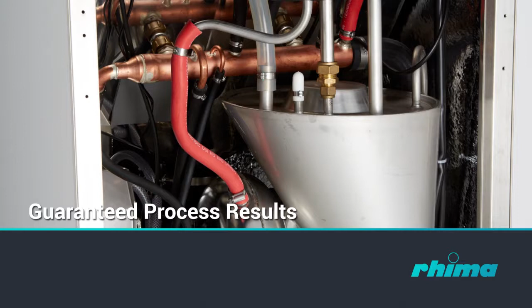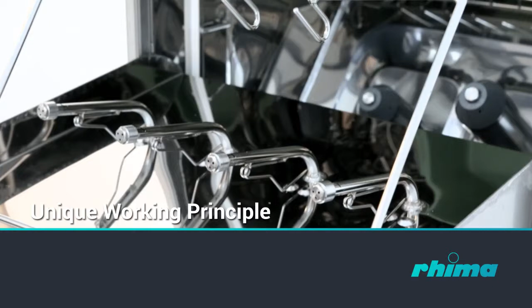Process results are guaranteed. Water pressure for washing is supplied by a high-powered 600 litre per minute recirculation pump. Detergent is injected into the recirculated wash water by the automatic integral dosing system. The unique working principle facilitates cleaning and steam disinfection of the entire system, including wash chamber, water tank and drain outlet, with the minimum usage of water and energy. The steam disinfection phase is generated by the integrated non-pressurised boiler and is directed through the water tank outlet and internal pipework.